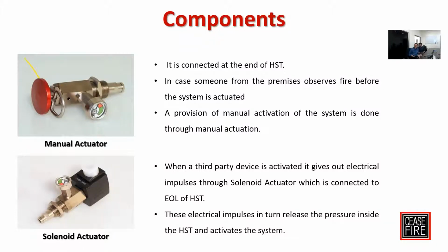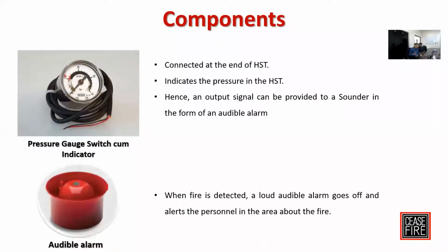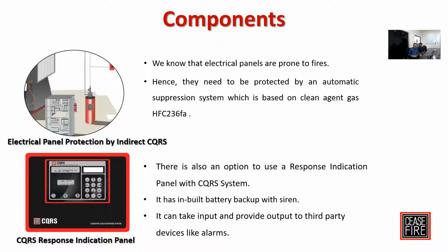So the tube detection is there for the mechanical actuation, and in case they also want electrical actuation, we can connect their smoke or heat detector along with the solenoid, and the solenoid will remove the pressure from inside the tube, and the system will be automatically actuated because of the indirect valve. That's the pressure switch, the audible alarm as an output. This is optional. If you want, we can provide it. If you don't want, they can be removed.